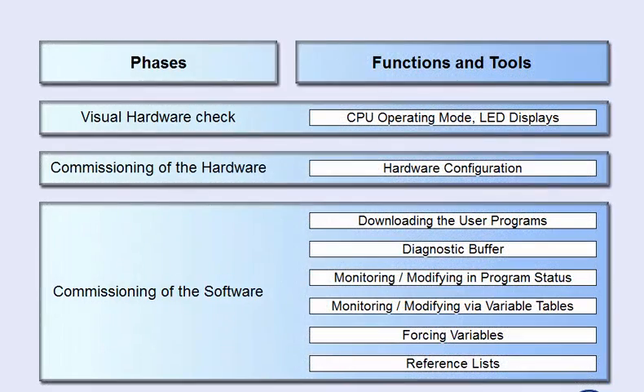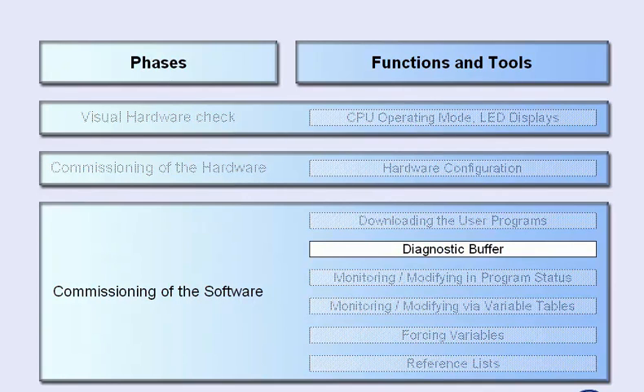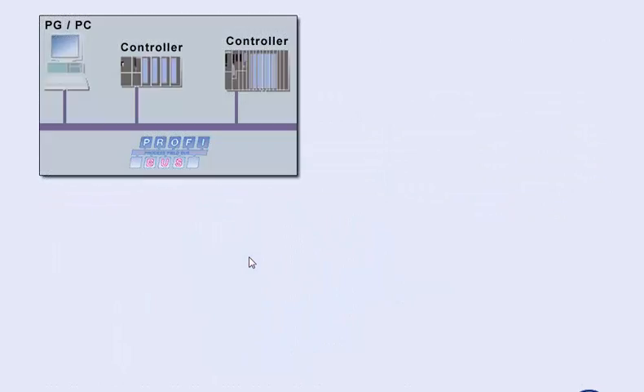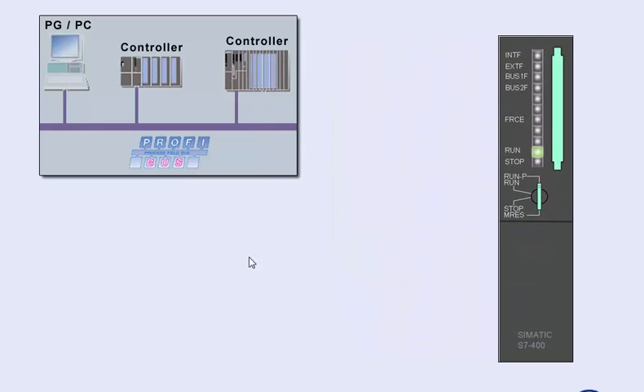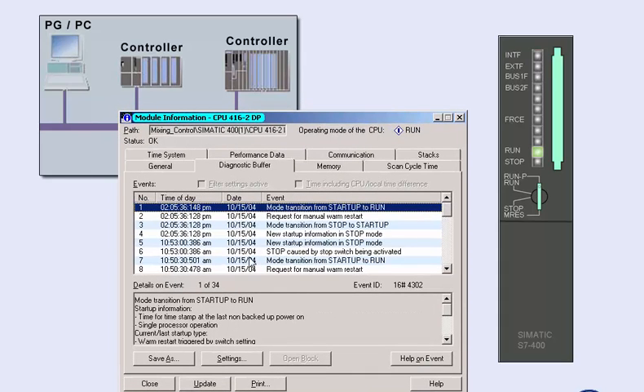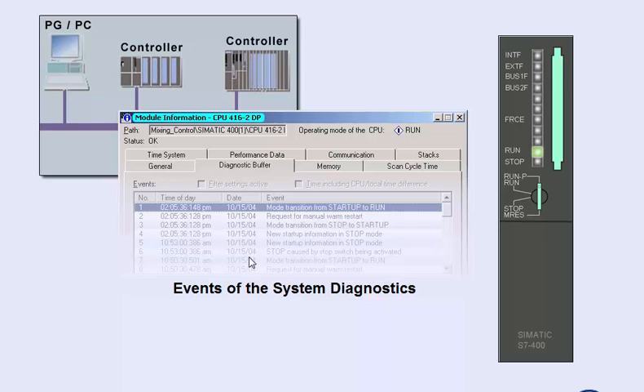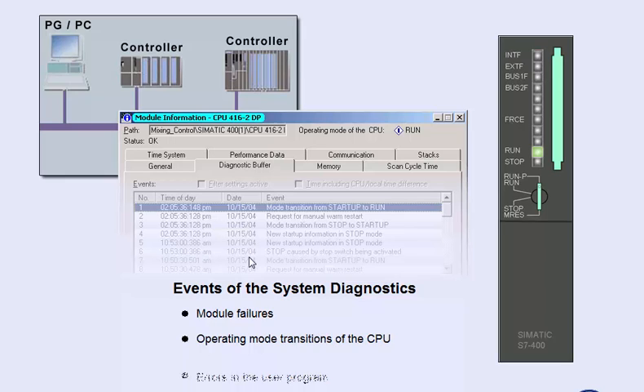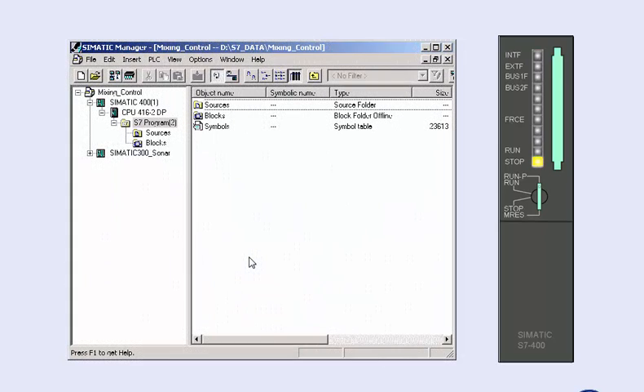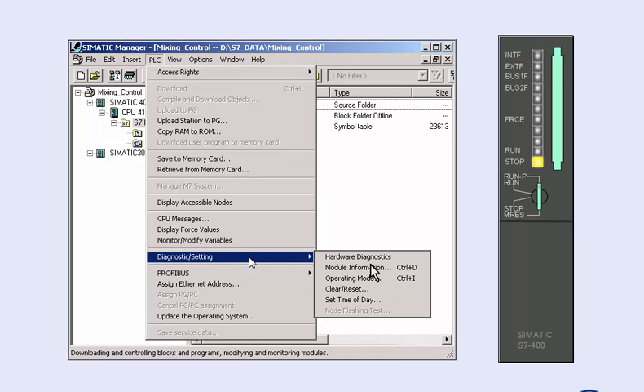The diagnostic buffer provides one of the most important aids to system diagnostics. It can be used for reliably diagnosing and localizing errors in the program and also the hardware during the commissioning phase as well as later plant operation. The diagnostic buffer is located in the system memory of the CPU and can be read any time with the SIMATIC manager. Designed as a ring buffer, all important events are saved — for instance, module failures, operating mode transitions of the CPU, or errors in the user program leading to stop mode. If during commissioning the CPU changes to stop mode, the cause will be given to you in the diagnostic buffer, which you access via the module information of the CPU.